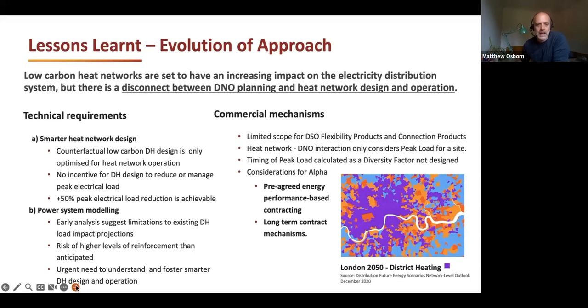Looking at technical requirements, heat network designs are made in isolation and only consider how to serve peak heat loads in the most cost-efficient way. Currently there are no commercial incentives for heat network designers to develop systems that reduce or manage peak electrical loads other than for their own cost efficiency. However, we've identified that it's possible to adjust designs to lower peak loads by up to 50%.